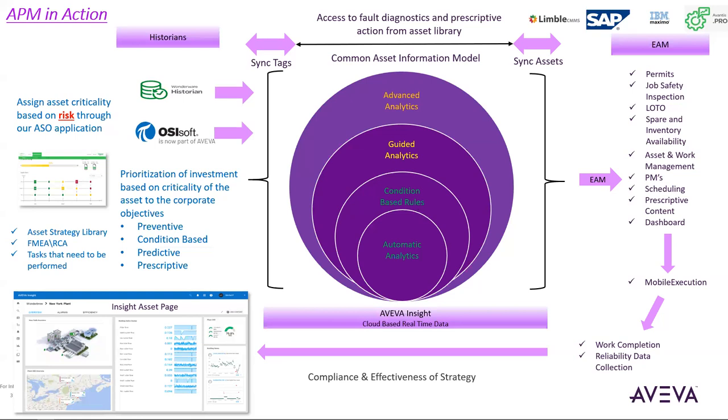If these thresholds or if these points, any, all, have been met, I want to notify, send a message to George, please, text message, email. I want to raise a work request in my Maximo or my Avantis or my SAP or my Limble system. And in that work request, I'm going to have very focused instructions on how to fix the problem that we've detected. Okay. It's rules-based. It's simple. I tell clients, if things break down and you know why, condition-based rules is very effective. If things break down in your plant and you don't know why, then guided analytics might be a help.